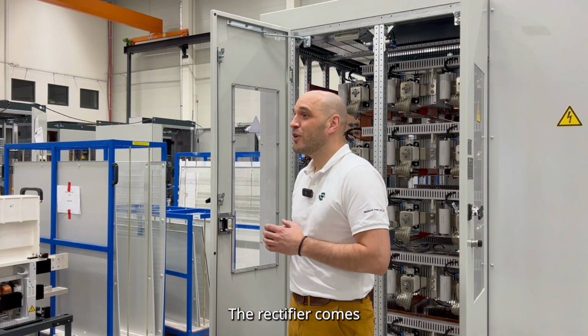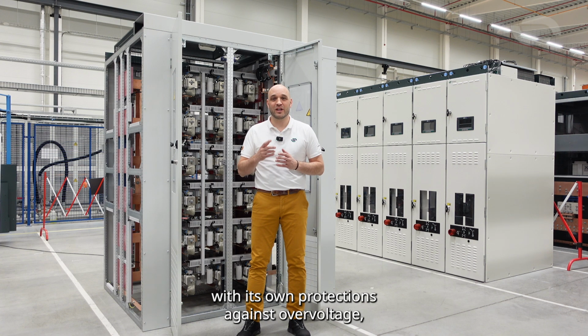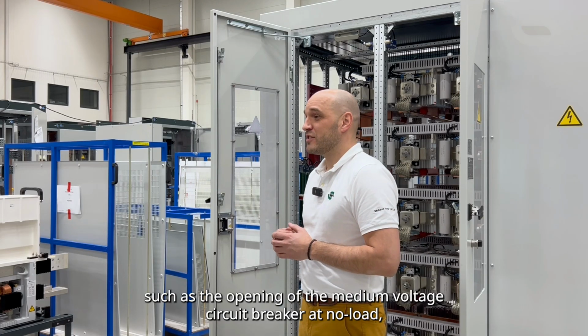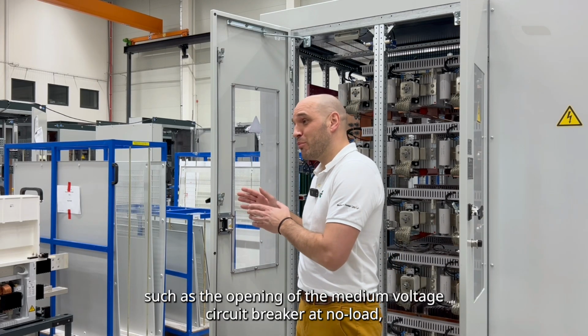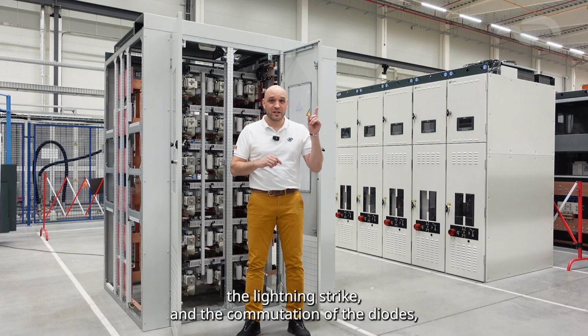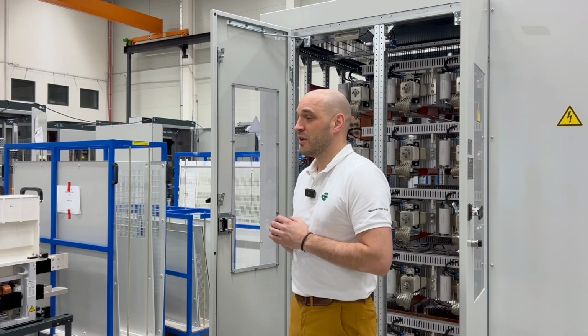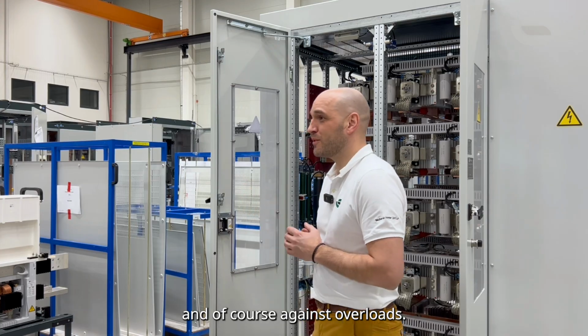The rectifier comes with its own protections against overvoltage, such as the opening of the medium voltage circuit breaker at no load, the lightning strike, and the commutation of the diodes, and of course against overloads.